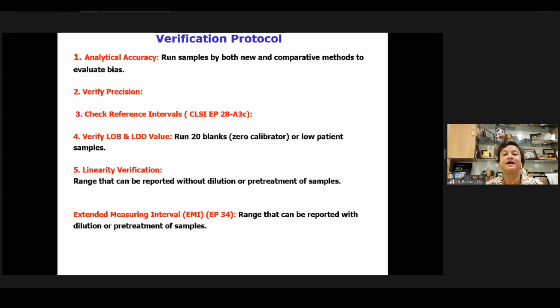Because of that, when we are doing verifications, it is very important to verify the reference interval. Now verify the LOB and LOD, limit of blank and limit of detection, by running 20 blanks or zero calibrator or low patient samples. Then linearity verification. I remember during my CAP inspection, I had done everything, but I forgot. I thought we were taking linearity surveys in CAP, so why do we need linearity verification before releasing any patient samples? But I got a deficiency because of that linearity verification.